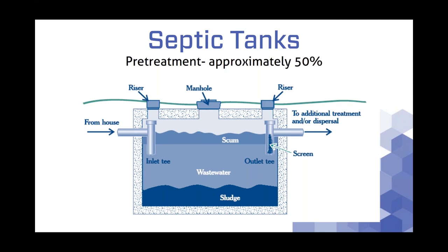Oftentimes we'll use a screen or filter on the outlet end to screen some of the solids. One important thing to note about septic tanks is they're very good for pretreatment, but you're going to get somewhere between about 25 to 50% treatment efficiency from them. So the raw waste coming in from the house will be treated to about 25 to 50% efficiency by the time it goes out. In conventional septic systems, final dispersal into the soil does the remaining treatment. We'll talk about primary treatment — septic tanks — and then advanced or secondary treatment as we move through the presentation.